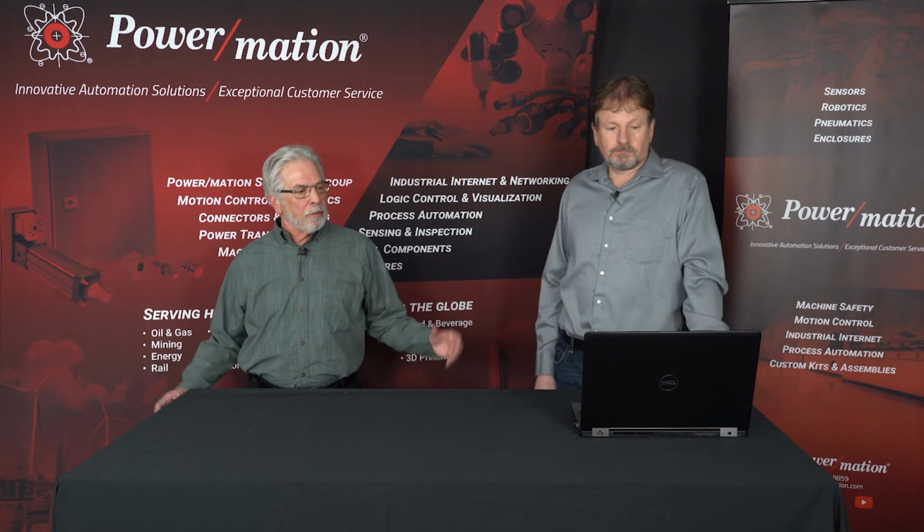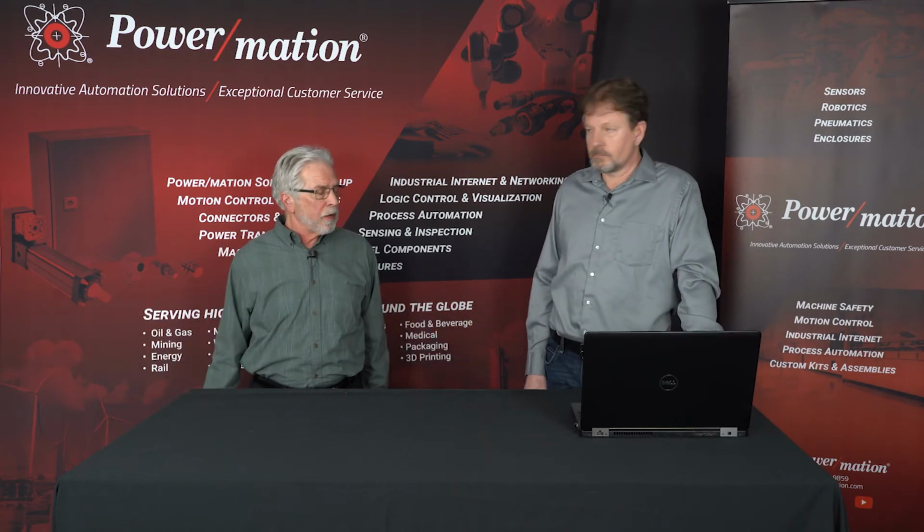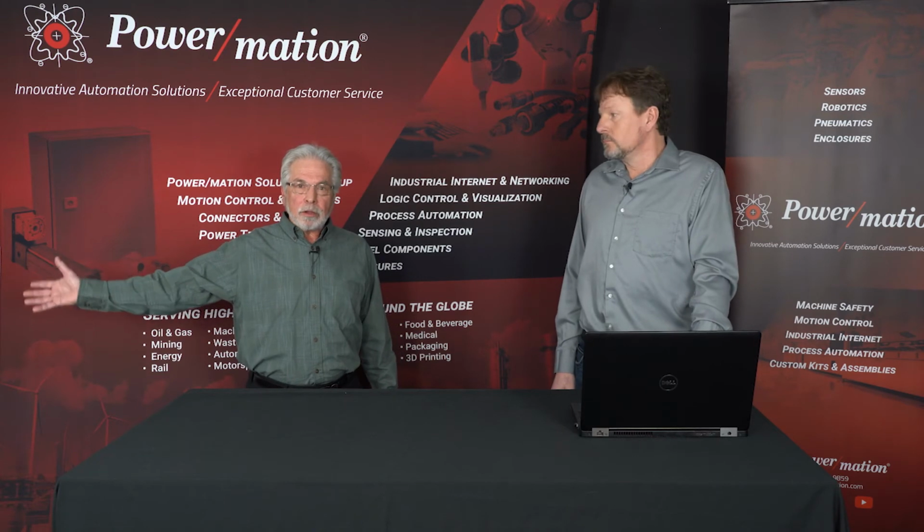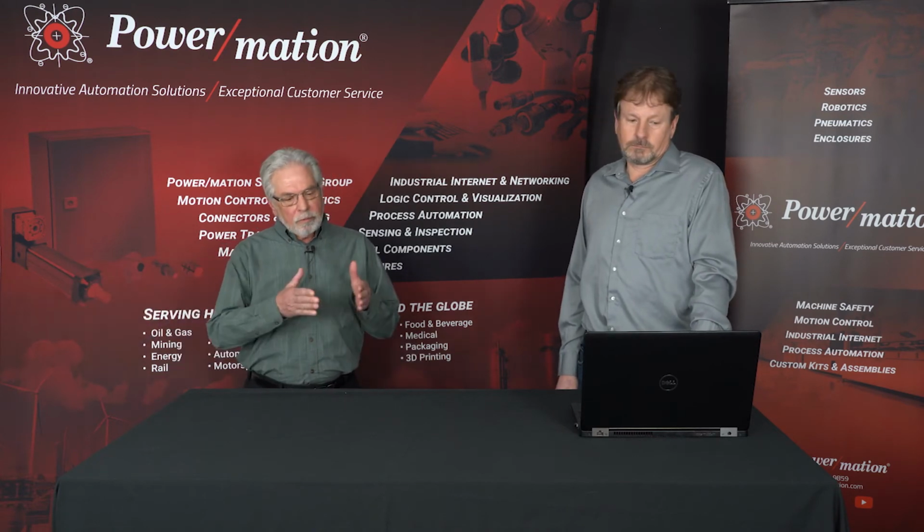So actually being able to do two power feeds from two different directions, communication from two different directions. Maybe we set up a control system with power on one end of the tunnel, control system with controller and power on the other end of the tunnel, and now a collapse in the middle or on one end or the other still gives us control of that tunnel.